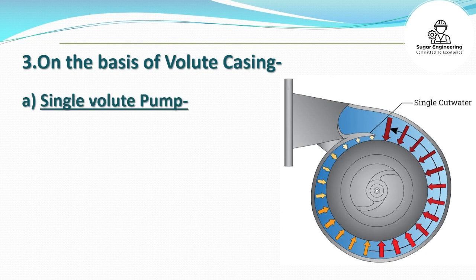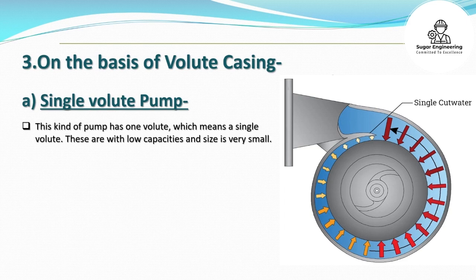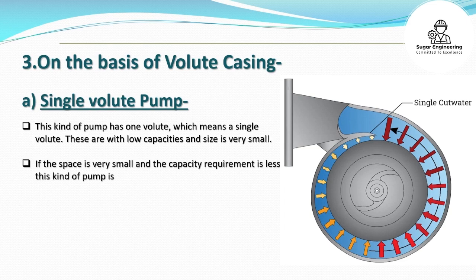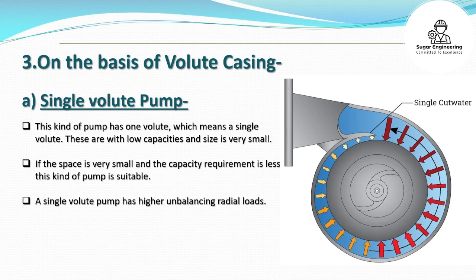On the basis of volute casing: A. Single volute pump. This kind of pump has one volute — a single volute. These pumps are of low capacity and very small in size. If the space is very limited and the capacity requirement is less, this kind of pump is suitable. A single volute pump has higher unbalanced radial loads.